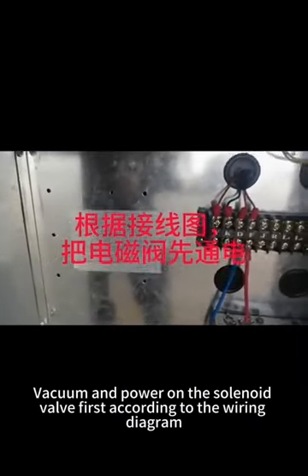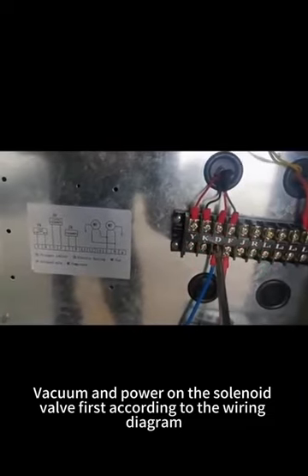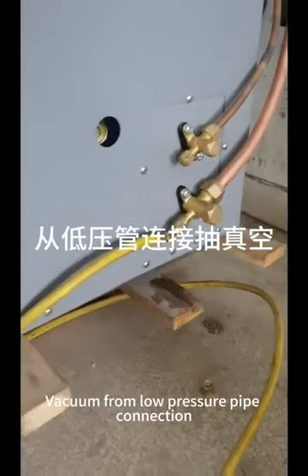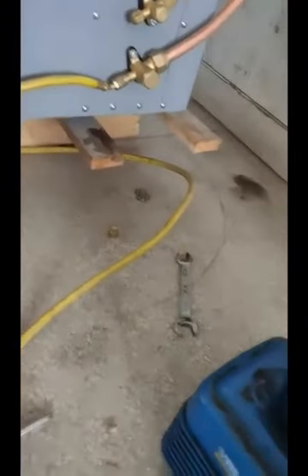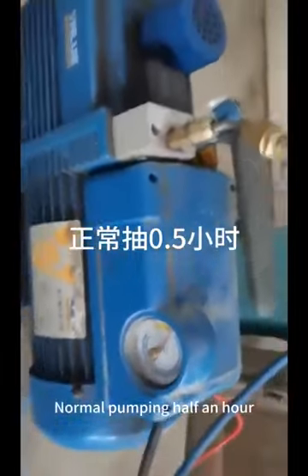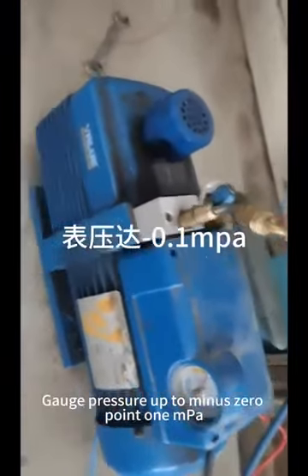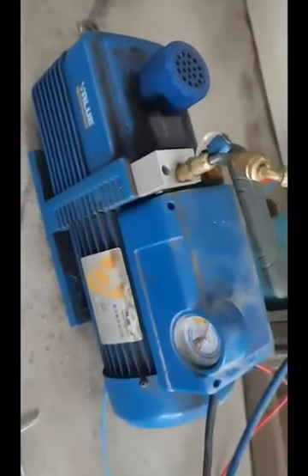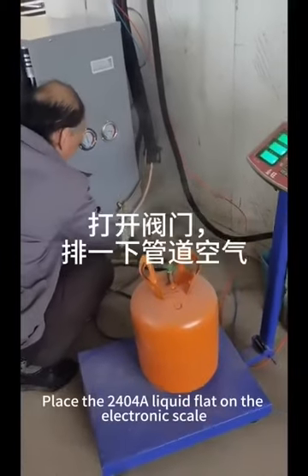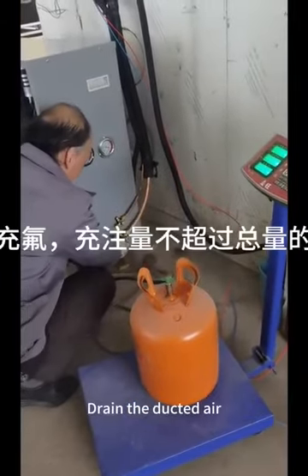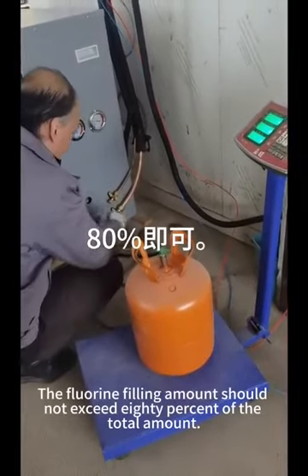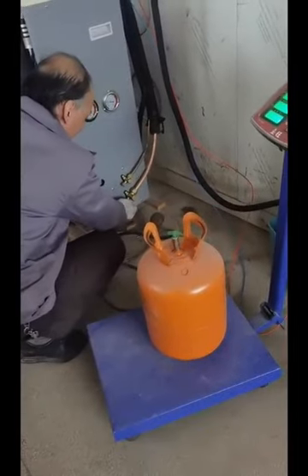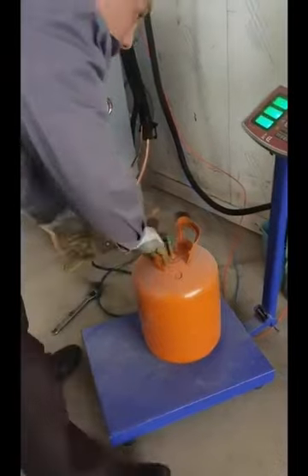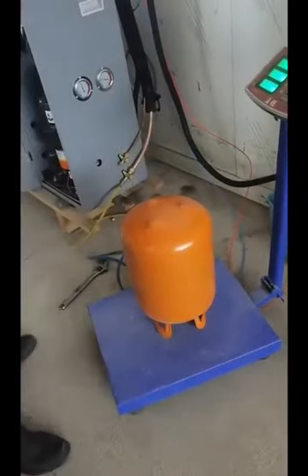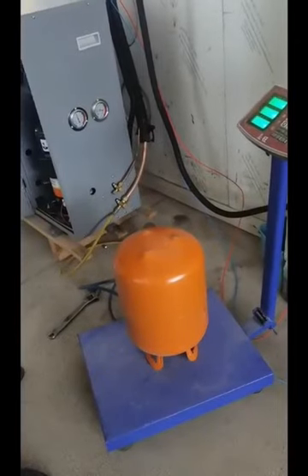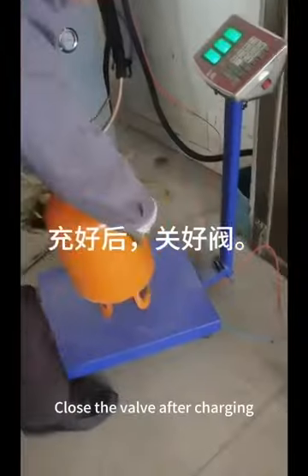Condensation system. Vacuum and power on the solenoid valve first according to the wiring diagram. Vacuum from low pressure pipe connection. Normal pumping half an hour. Gauge pressure up to -0.1 MPa. Add freon R404A. Place the R404A, liquid flat, on the electronic scale. Open the valve. Drain the ducted air. The fluorine filling amount should not exceed 80% of the total amount. Refer to unit nameplate. Close the valve after charging.